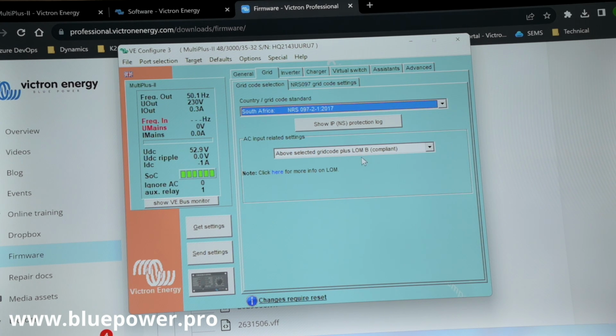The next option we've got here is the AC input related settings. Here we've got LOM detection, or loss of mains detection. What that is, it measures how quickly the voltage drops or the frequency drops, or if it rises above the input parameters on the units. With LOM detection switched on, the unit is going to disconnect quicker from the power source if it sees that the voltage looks like it's starting to drop or the frequency is starting to drop. Then it's going to disconnect quicker to try and protect your loads from any low voltages or unnecessary frequencies.